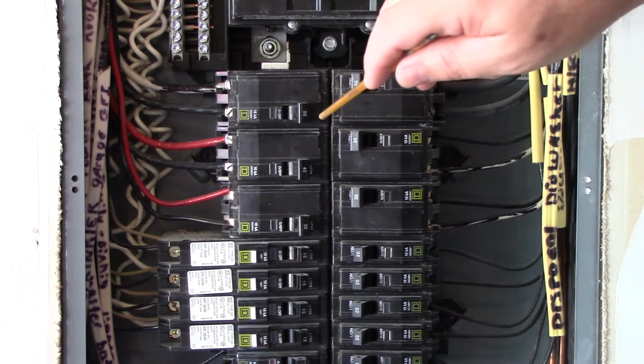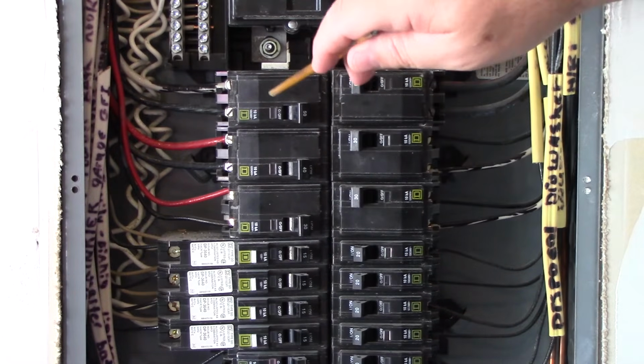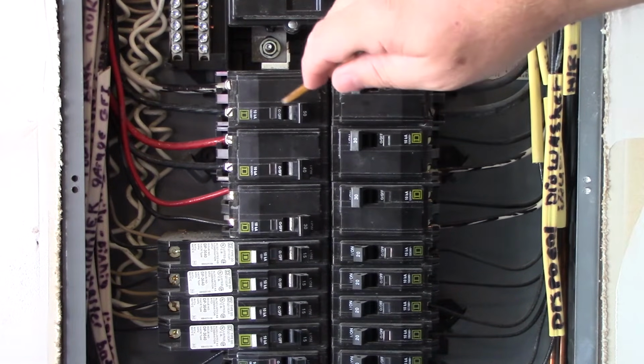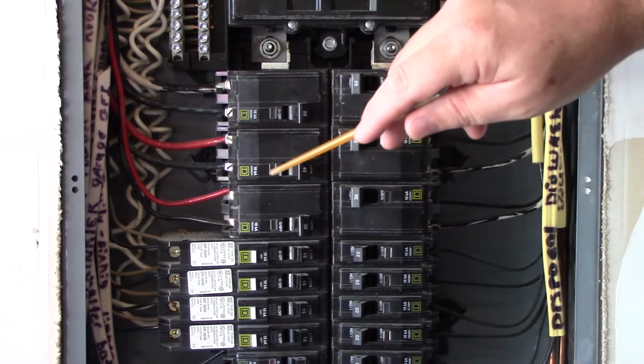So we got that okay. Here's a 50 amp. We have a 6 copper on this as well, which is good, 55 amps. So we got it on a 50 amp breaker. We're good here. This is specific, so this follows the normal sizing rules under 240.